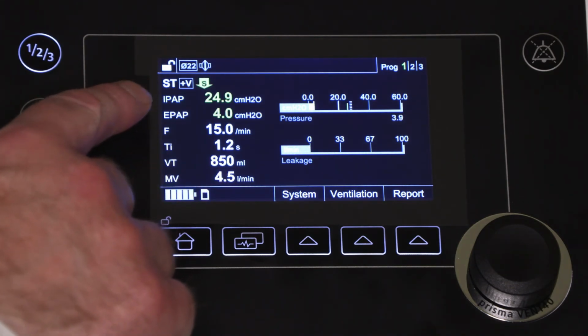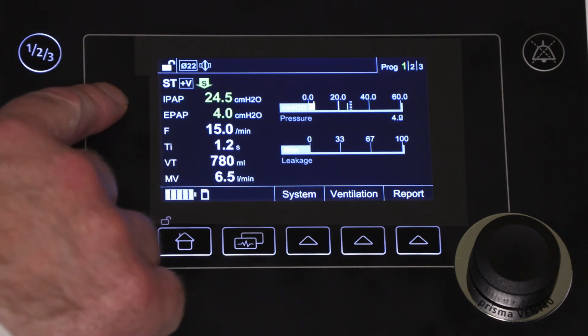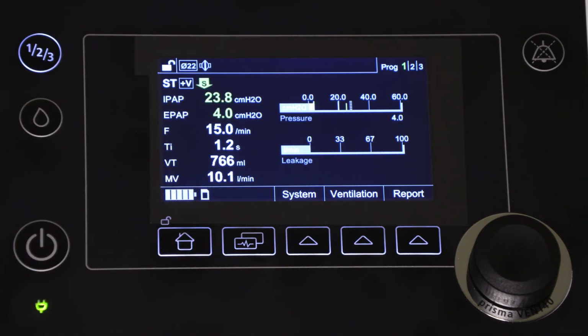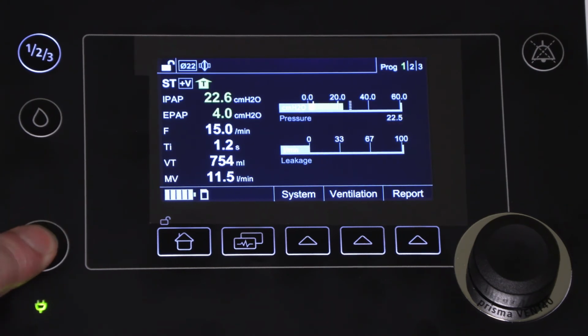It didn't need the full 8 centimetres we allowed and only used a portion of that extra IPAP. In fact, the IPAP will now start to decrease and will keep decreasing back to the prescribed set IPAP, unless the ventilator detects another drop in the patient volume, in which case it will start to increase again. To stop therapy, press and hold the power button.